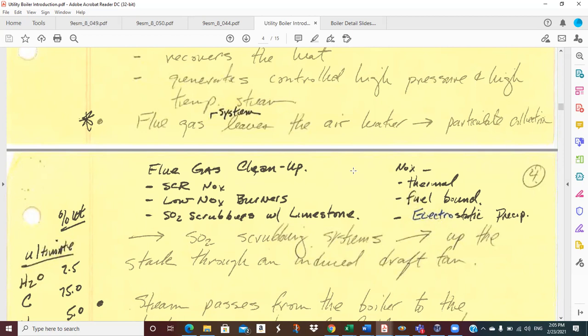SO2, sulfur dioxide, you scrub that, a water bath typically, a wet scrubber. They have dry scrubbers, but I think most of the power industry uses wet scrubbers. And use limestone. CaCO3 will capture the sulfur. It turns into a solid product that you can capture, and you can even recycle the sulfur if you want to. So we can use bag houses or electrostatic precipitators for particulate removal. So anyway, we'll spend more time on that.